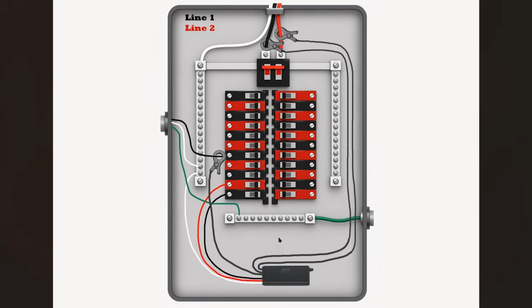You'll want to decide where to install the F3000 because it matters which side it's on. If you want to backfeed to line 1, install it on line 1, and it will backfeed to every one of these black circuit breakers to offset the load for those circuits. If you install it on line 2, represented by the red circuit breakers, it will backfeed to all of the red circuit breakers. That's how it's able to offset the loads in your house.